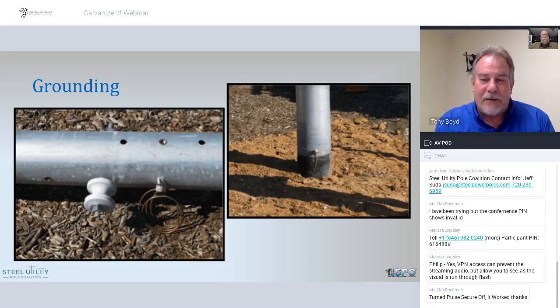I think I got a question one time a long time ago about leaving the coating off of the bottom of the pole, and that's between you and the manufacturer. I think I would rather have that coating on the bottom to protect the bottom of the pole and run an exterior ground. So it's up to the user how you want to do it. But we take a wooden pole and we run a copper ground rod down and staple it to the pole all the way down the pole. So using the pole as a ground continuity, then we don't have to use as much copper. So there you've saved a little bit of money.